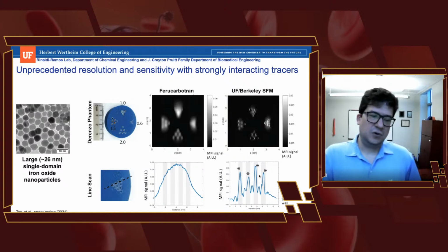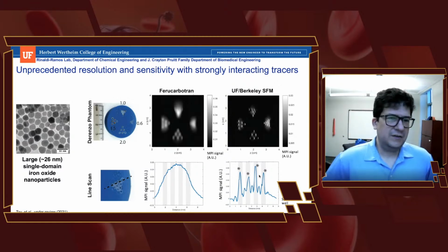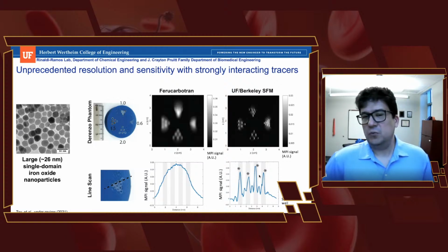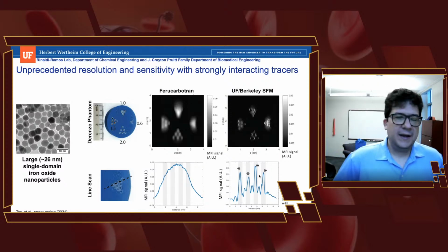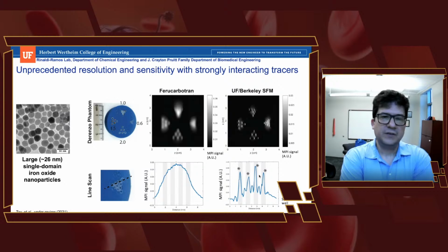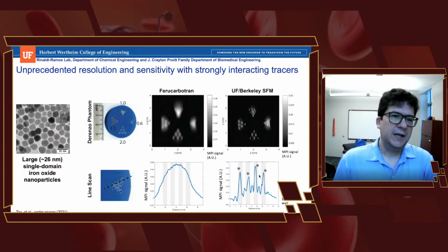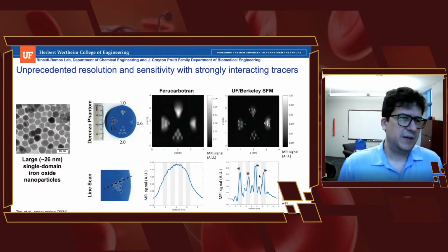And so analysis of the point spread function suggests, and this is in the paper and not in the slides, that we can obtain particles with full width at half maxima as small as 1.51 millitesla. And so if you were to apply a 5 Tesla per meter gradient field, those particles should be able to have a resolution between 150 to 200 microns. And so that's very exciting because that's not something that's been achieved before in MPI. Also, it has important implications for development of clinical scanners, which I'm not going to get into now.